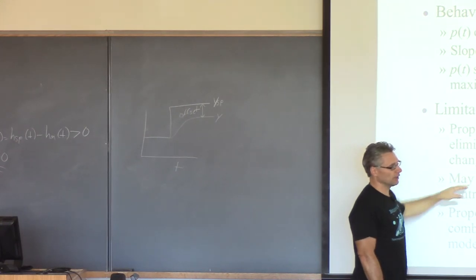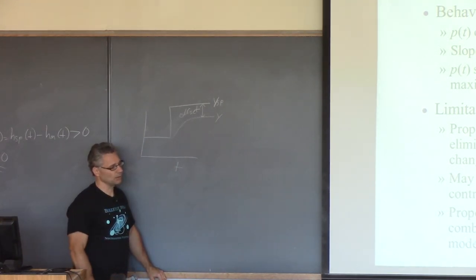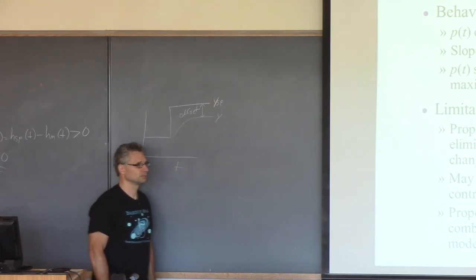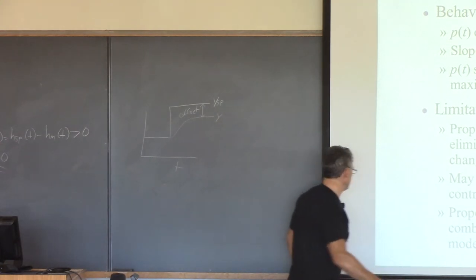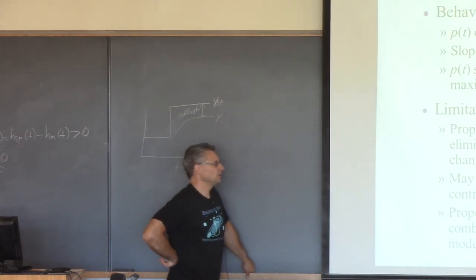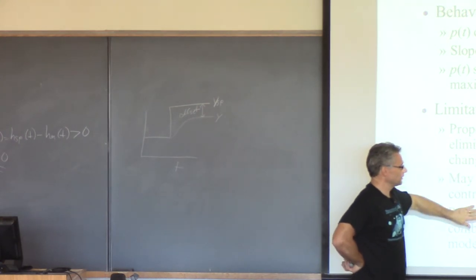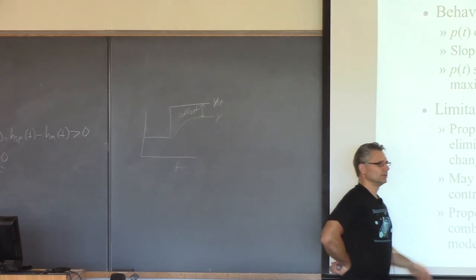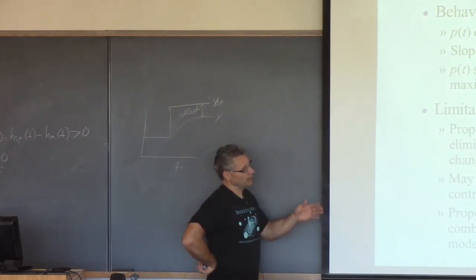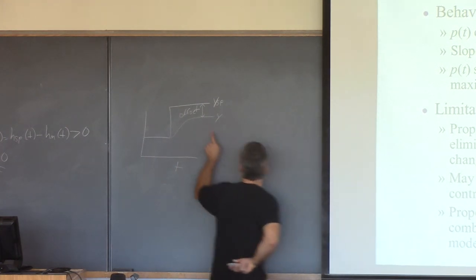Offset might be acceptable for liquid level — where the primary concern is just that the tank not be too empty or too full — but most operators wouldn't like it. In a plant, operators operate the plant, not the engineers, and you have to implement things they understand and will use. So we're going to combine proportional control with integral control: in addition to the term proportional to the error, we add a term proportional to the integral of the error, which will eliminate offset.